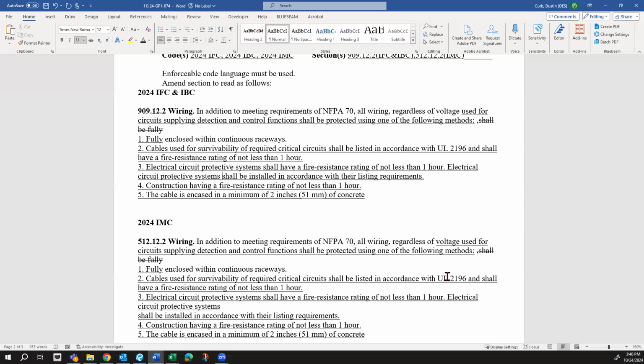Right now, you could call any AHJ and ask if they've ever inspected this. The only AHJ doing any kind of electrical inspection for this kind of stuff is Bellevue with their city inspectors, and they have exceptions to what they actually consider raceway. They allow MC cable, which by definition in NEC is not a raceway. So it's this really convoluted thing, trying to do it right by installing it right, but at the same time, that's not how every job is getting done.